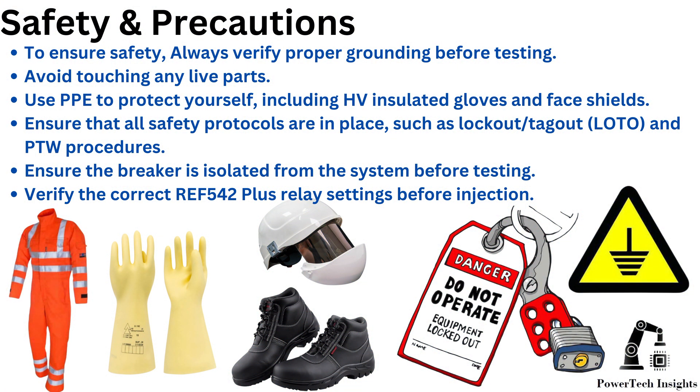Safety Precautions: To ensure safety, always verify proper grounding before testing. Avoid touching any live parts. Use PPE to protect yourself, including HV-insulated gloves and face shields. Ensure that all safety protocols are in place, such as lockout tagout and PTW procedures. Ensure the breaker is isolated from the system before testing. Verify the correct REF542 Plus relay settings before injection.